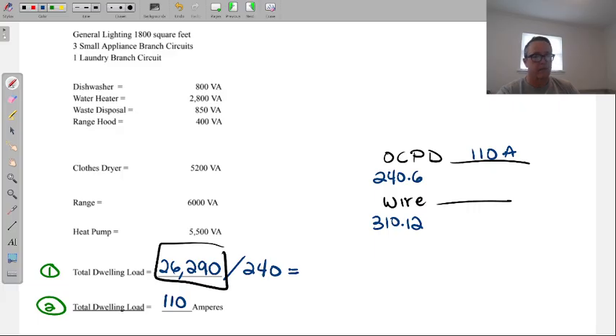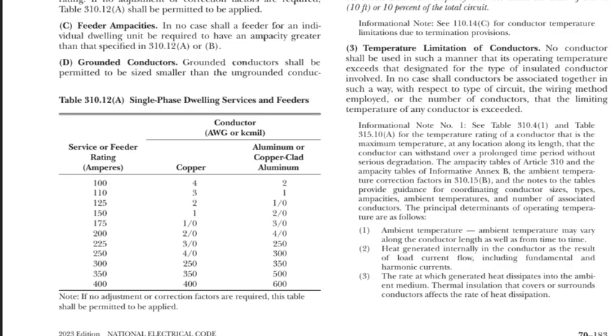Page 183. On page 183 you'll find the single phase dwelling service and feeders table. This is why we had to find our overcurrent protection device first. Because when you come to this table, you're not coming with the amperage that you calculated. You're coming with the main breaker that you chose.